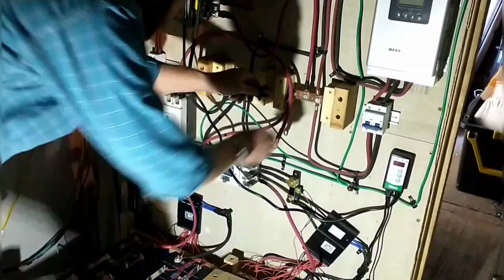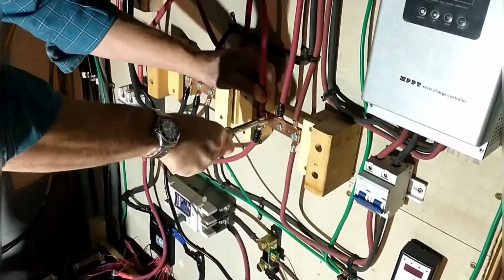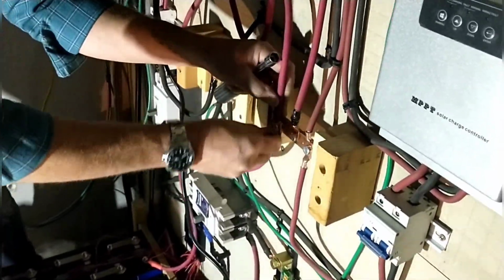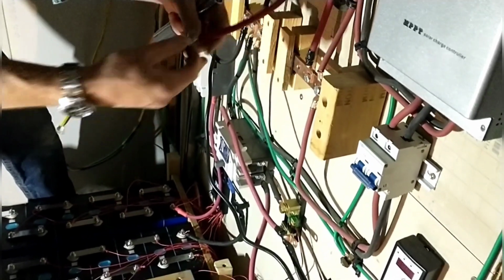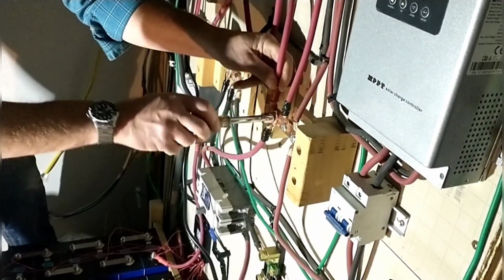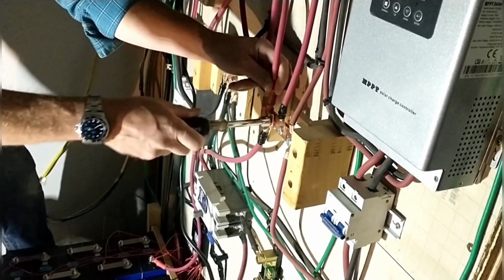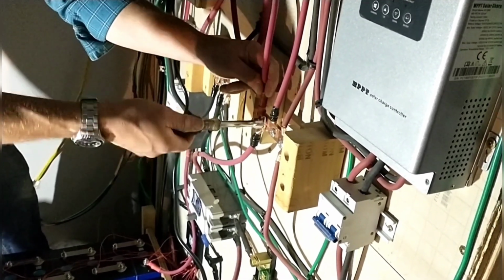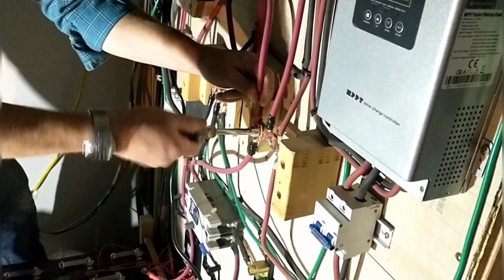I've already made all the connections up to the breaker, so all I need to do is run the wire from the breaker over to the bus bars. I'm using a 200 amp DC breaker, running 2-gauge copper wire over, and making the connections to the bus bar with a 3/8 inch bolt.